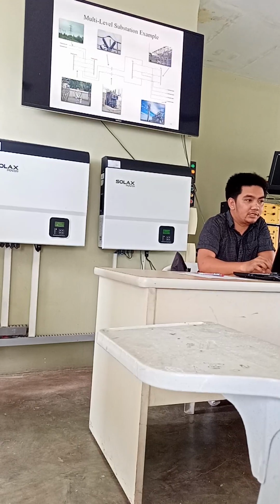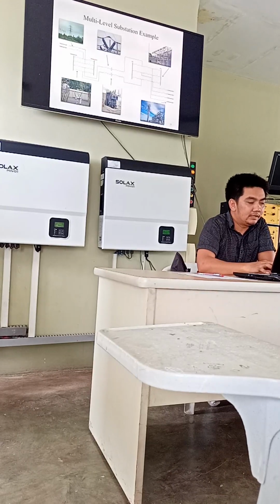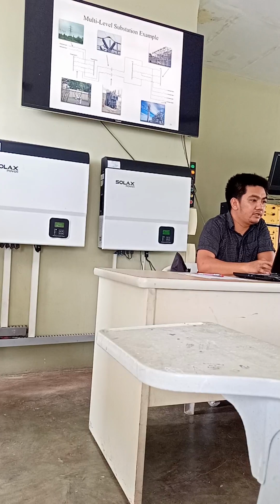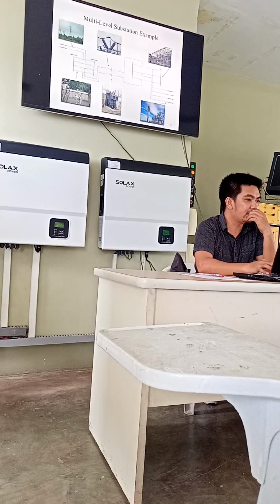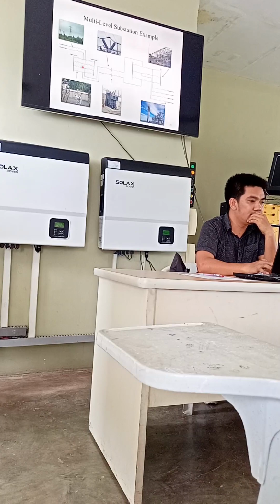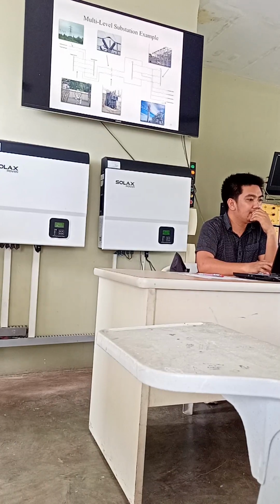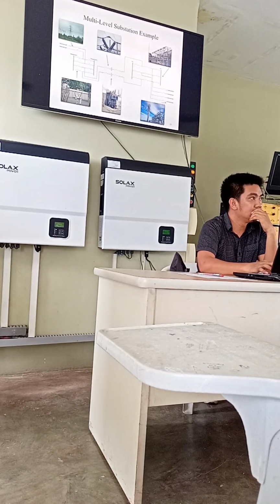Why is it a multi-level substation setup? Let's say these transmission lines are crucial assets that serve the generation's capacity, so that's where they enter. Since the bulk power enters here, this requires the highest reliability, so double bus double breaker is constructed here, because we cannot afford to shut down this substation or lose these capacities. So it must be double bus double breaker.